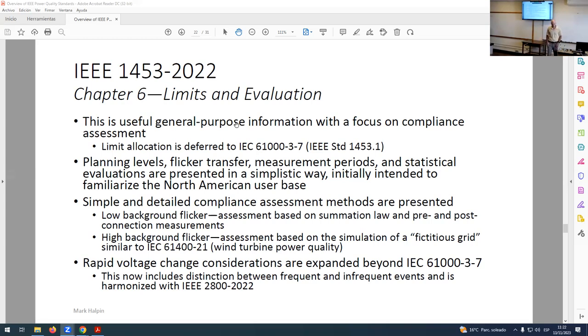Also, rapid voltage changes. What is a rapid voltage change? Well, the best way to think about a rapid voltage change is it's a change in RMS voltage, and it occurs often enough to think about, but it doesn't occur often enough to produce objectionable flicker, right? Don't we need to manage those kinds of events? Yeah, we do, right? Well, there are recommended rapid voltage limits in IEC 61000-3-7. So the fact we adopted that in IEEE, we got it covered. But the coverage in 61000-3-7 doesn't really apply, particularly in the U.S., to the way we are interconnecting, especially solar.